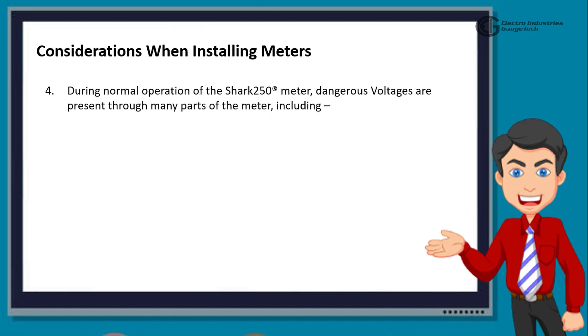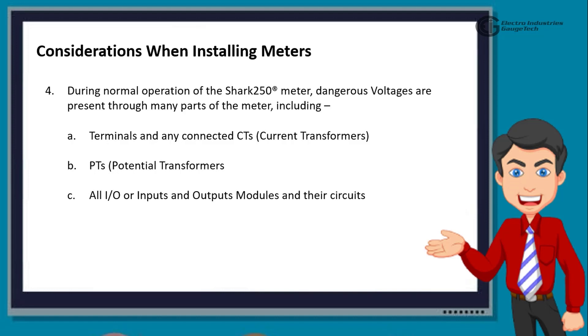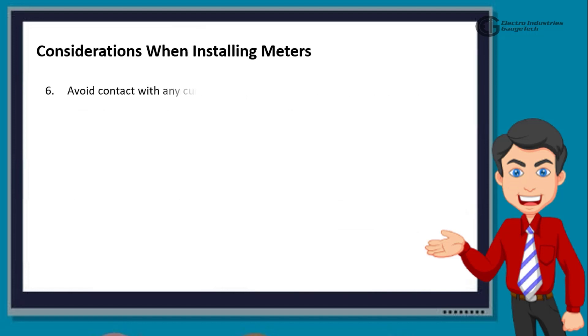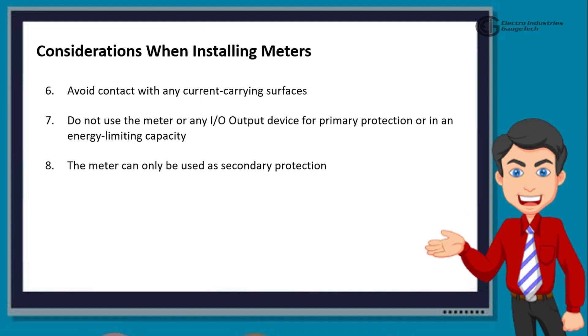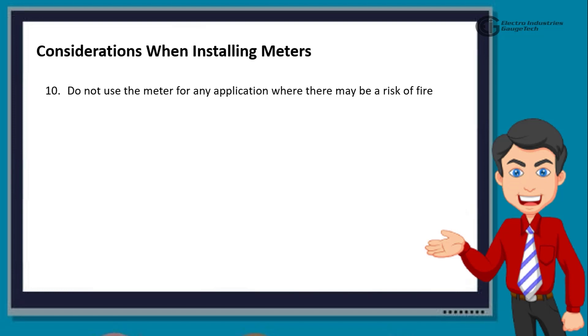During normal operation of the Shark 250 meter, dangerous voltages are present through many parts of the meter, including terminals and any connected CTs or current transformers, and PTs or potential transformers. All I/O inputs and outputs modules and their circuits. All primary and secondary circuits can, at times, produce lethal voltages and currents. Avoid contact with any current-carrying surfaces. Do not use the meter or any I/O output device for primary protection or in an energy-limiting capacity. The meter can only be used as secondary protection. Do not use the meter for applications where failure of the meter may cause harm or death. Do not use the meter for any application where there may be a risk of fire.